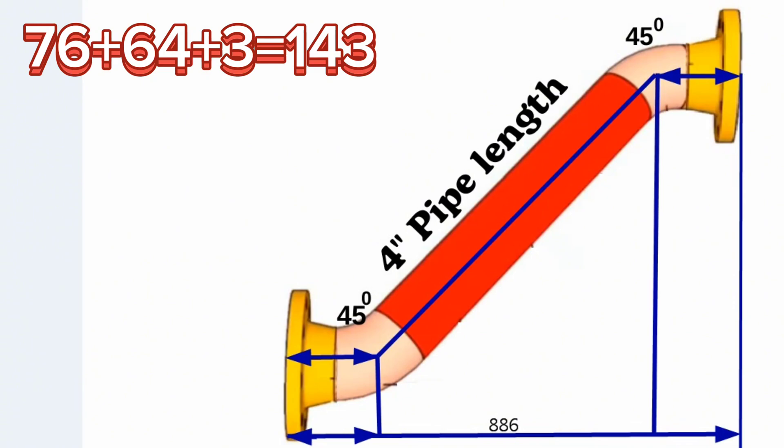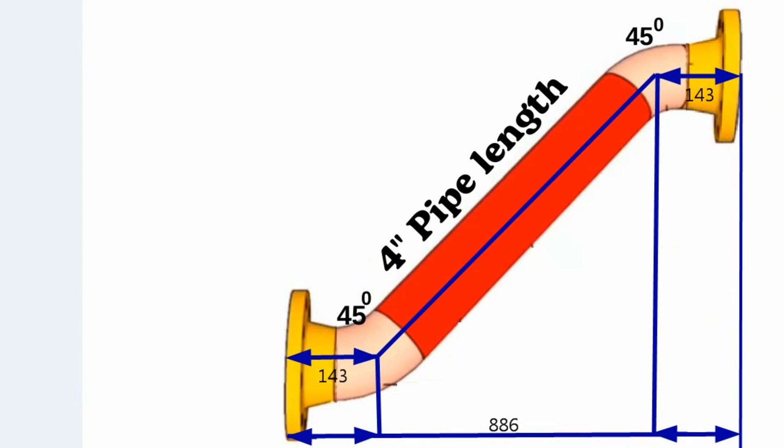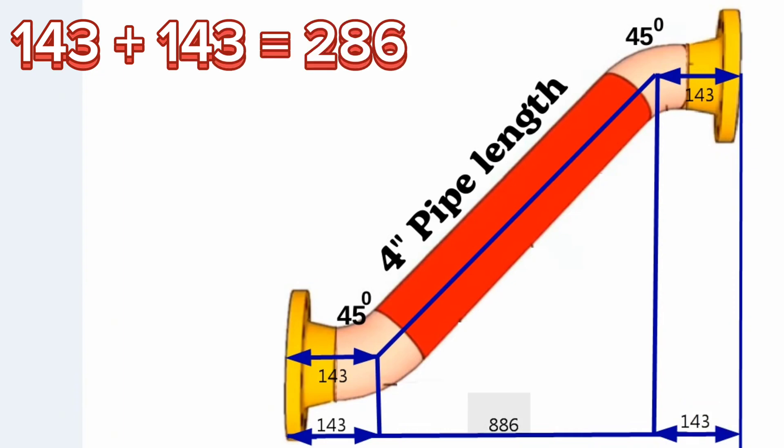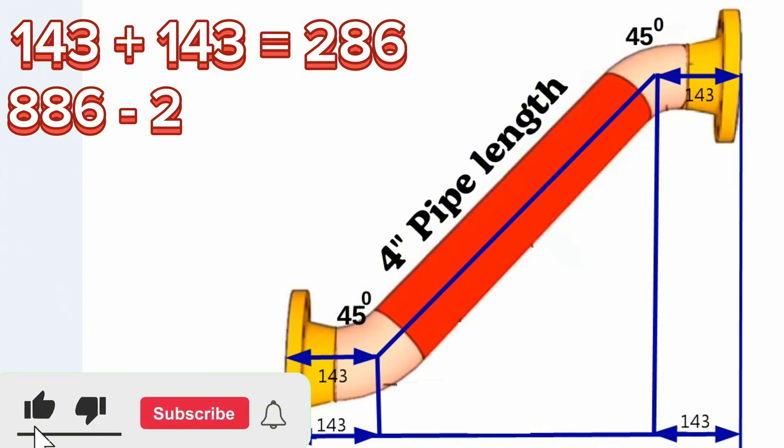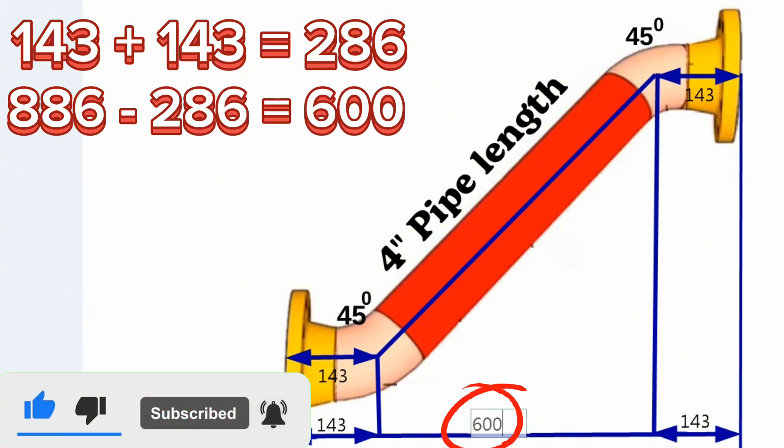The same rule on the other side of the pipe spool will be 143 millimeters. Two pieces of 4-inch weld neck flange and two pieces of 45-degree butt weld elbows and 2 times 3 millimeters gap equals 286 millimeters. Subtract 286 millimeters from the total length of 886 millimeters. The length of this distance is 600 millimeters.